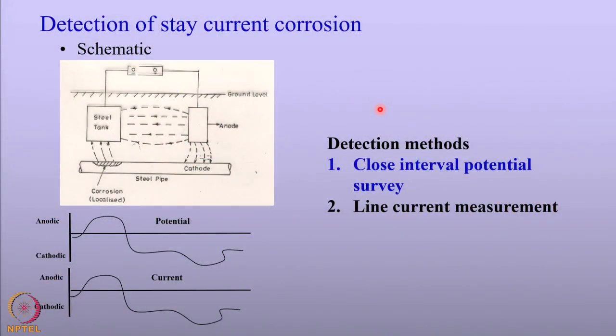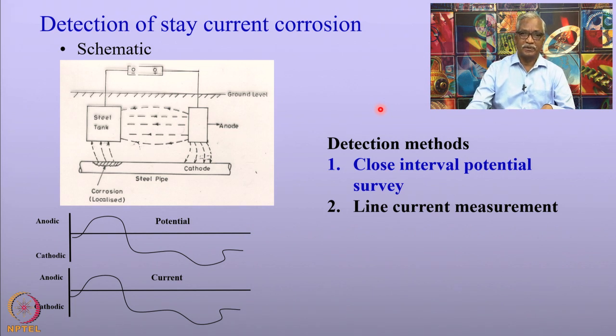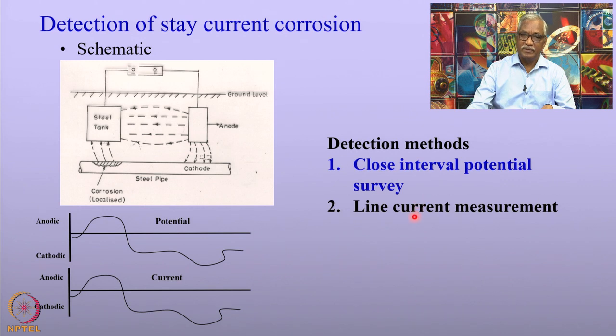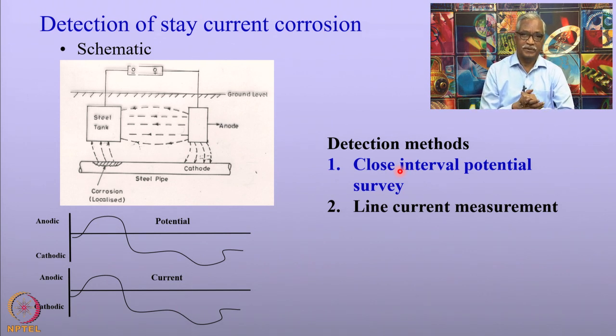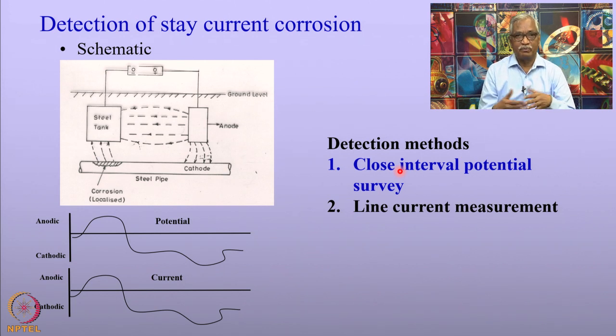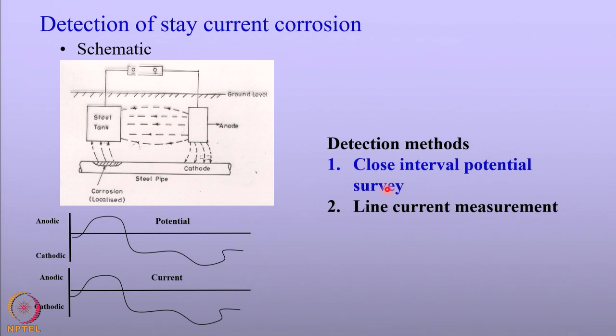Now let us move on to the important topic of detection of stray current corrosion. Recalling from a previous lecture on surveys to find out how underground pipelines suffer corrosion, we use two techniques: one is called close interval potential survey, and the other is line current measurements. We will see how these two techniques can be used to detect the location where buried structures suffer stray current corrosion. Please note that these are buried structures, not possible to inspect by visual means.